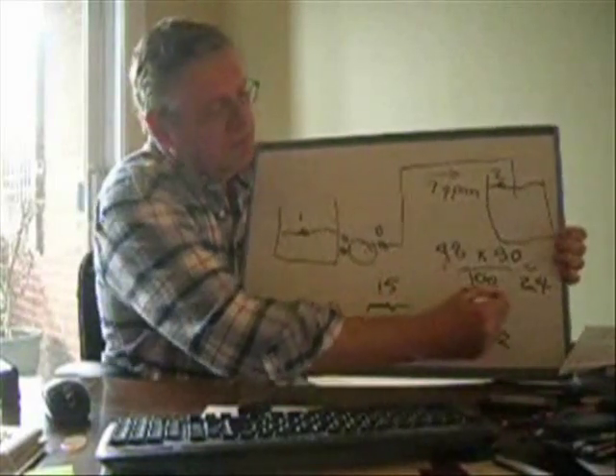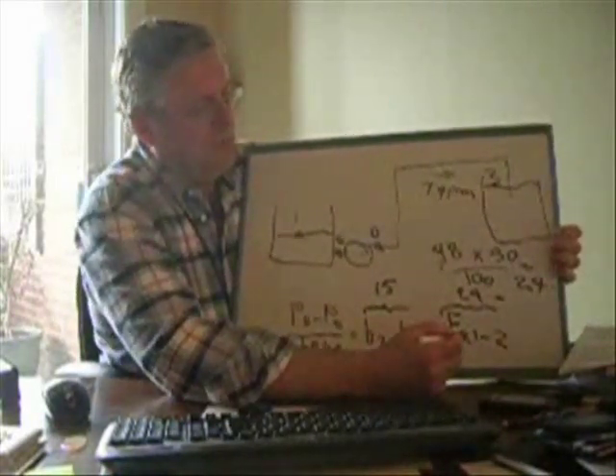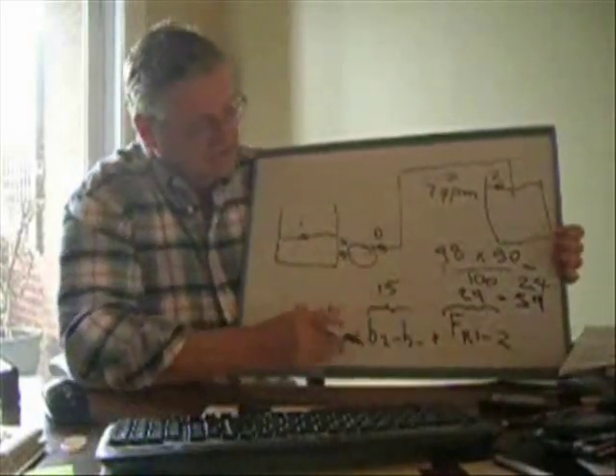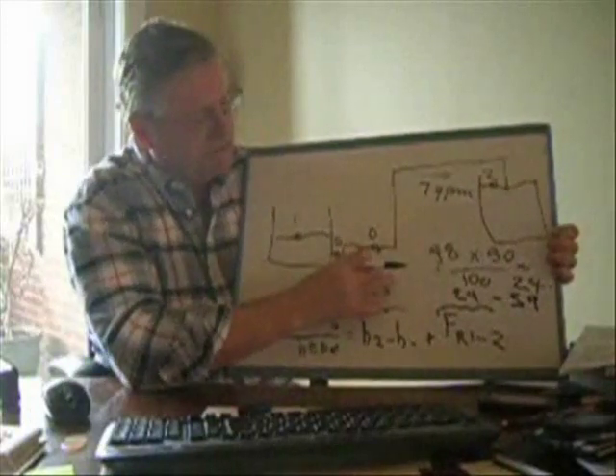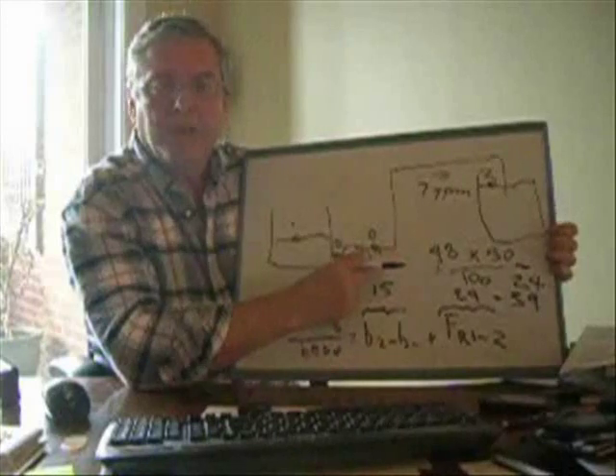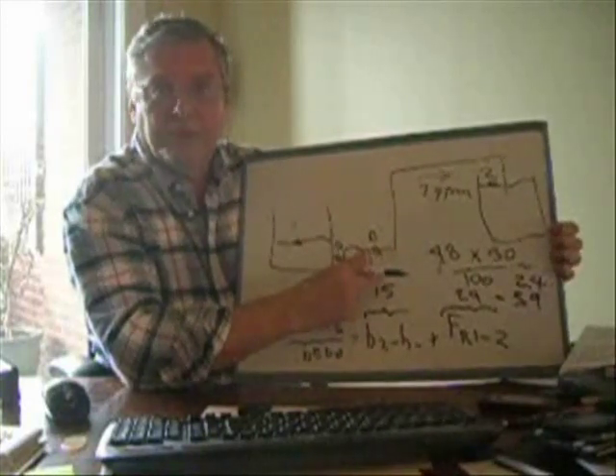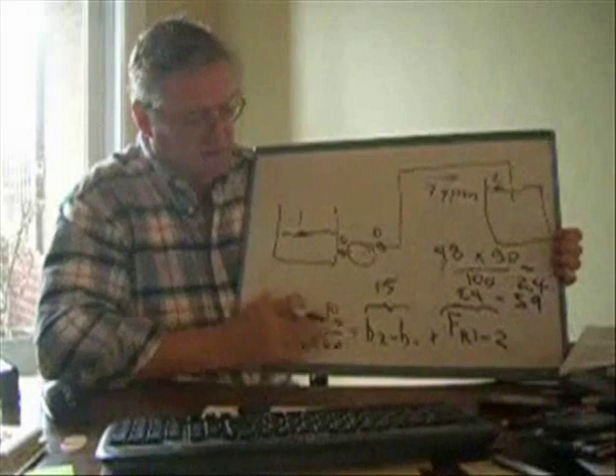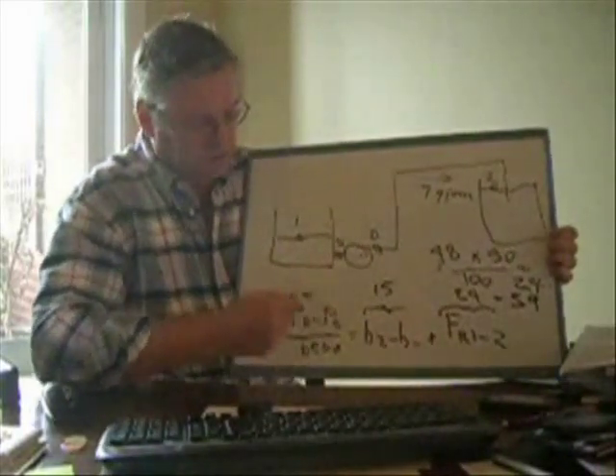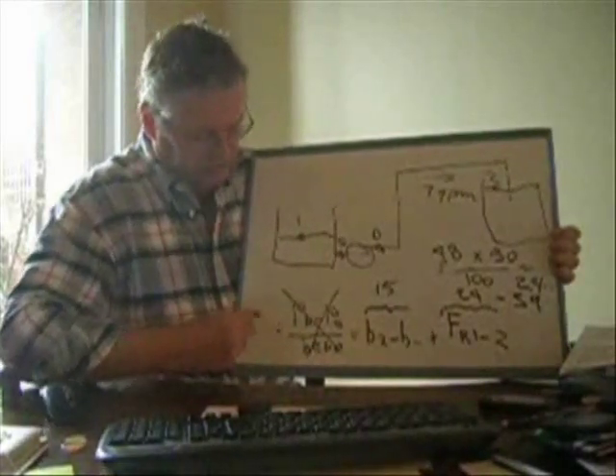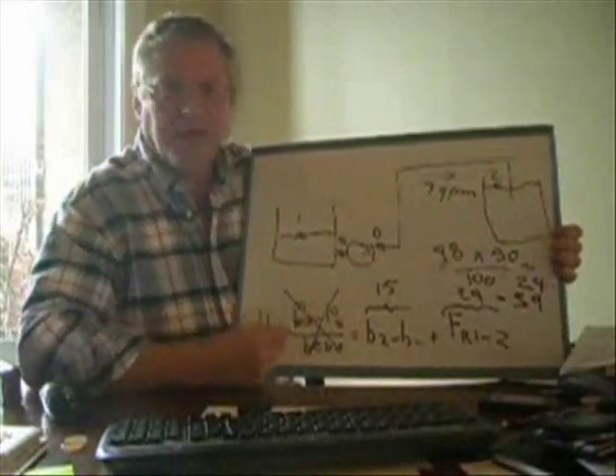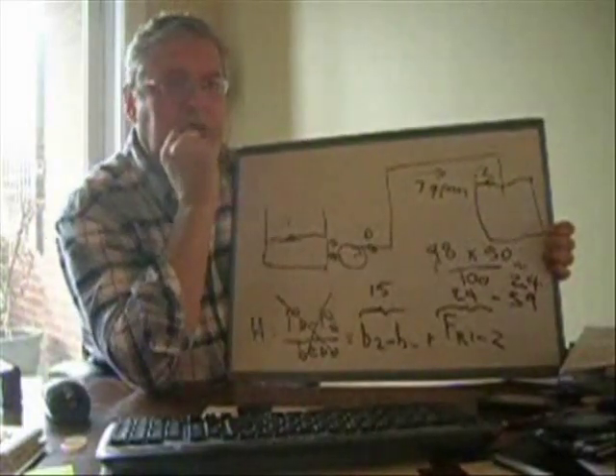So the total is fifteen plus twenty-four, that's thirty-nine. And that's telling us that this term here, the amount of pressure difference that the pump has to supply has to be thirty-nine feet. And that's going to be how we're going to size it, find the pump that will do the job. Now, this is an awkward term. This is feet, and this is feet. So this whole term here must be feet also. I'm just going to rename this. I'll call it H, and that's going to be H, and that term is known as total head.